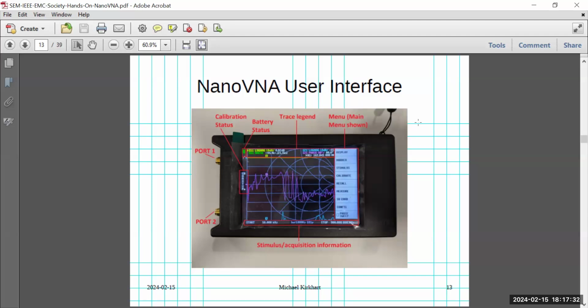Down here at the bottom, it shows you your stimulus information, like your start frequency, your stop frequency, the resolution bandwidth or IF bandwidth, which is fixed. You can't adjust that. That's something you can adjust on a high dollar VNA, but again, $100. And it'll tell you how many points are in the acquisition. Now a lot of them will only do 101 points. This one will actually do 401 points in an acquisition, but the price you pay for that is a longer acquisition time. If you want to try this, we will do the calibration with the normal 101 points.